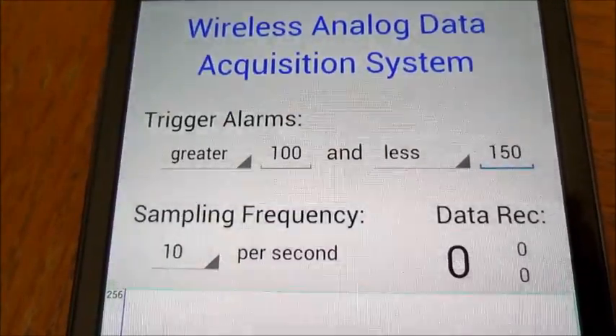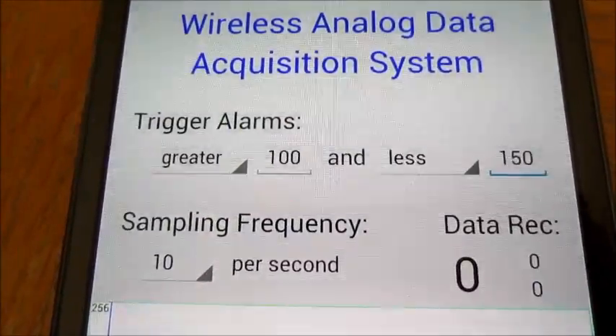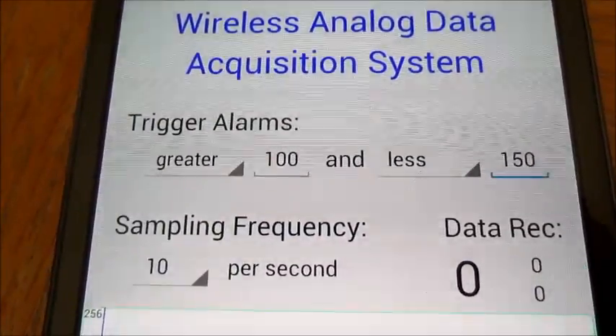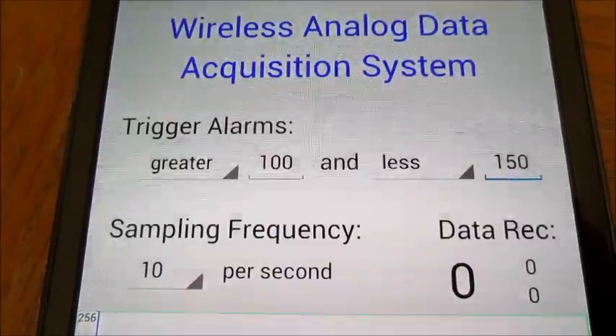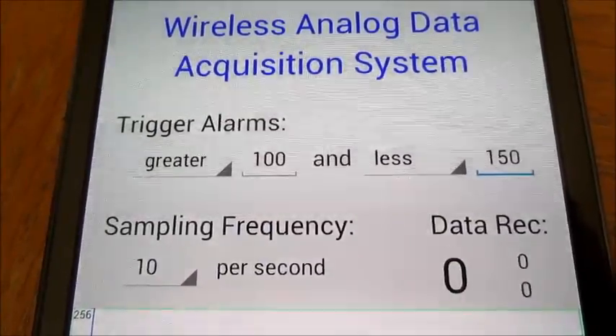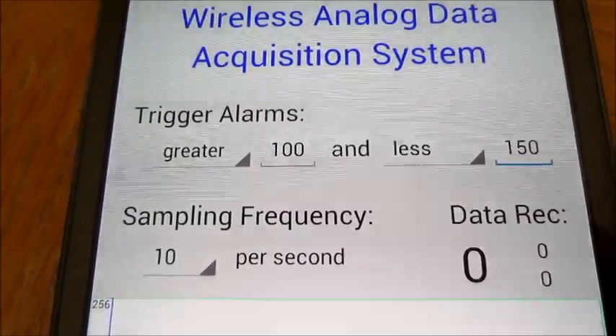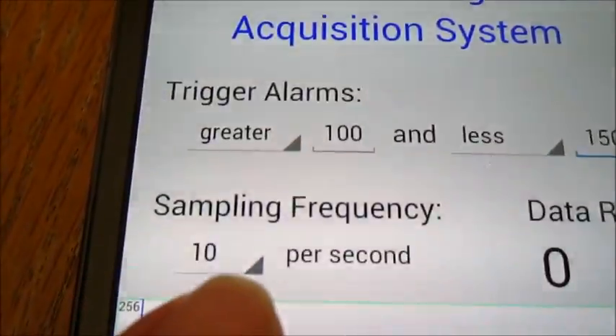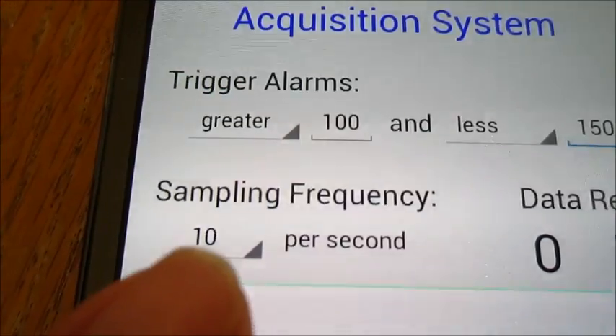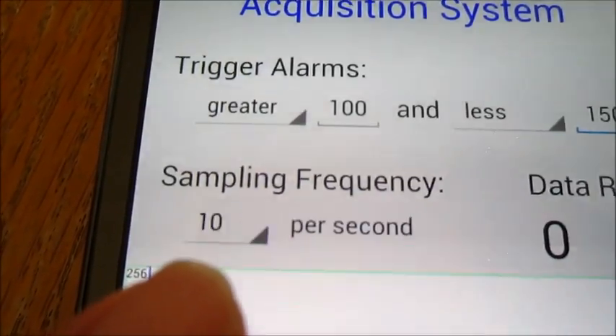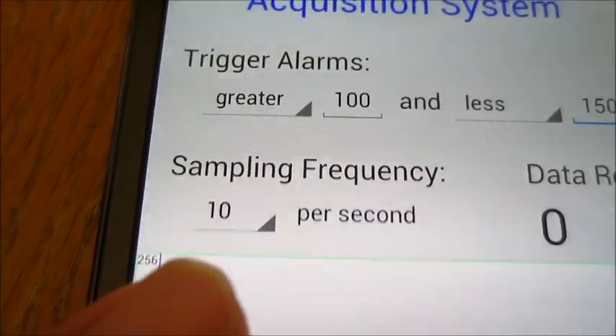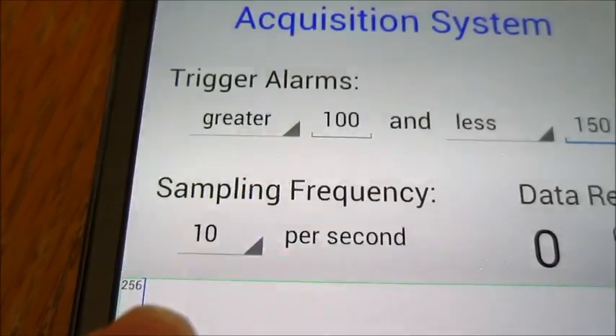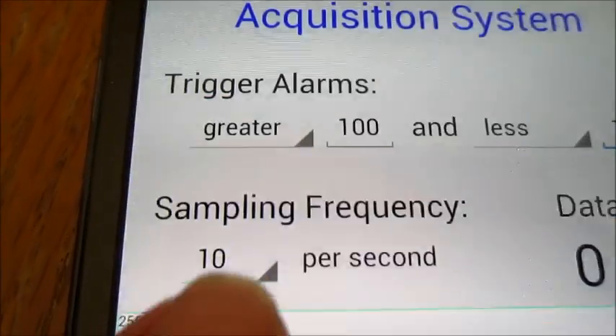Now the alarms are set to be greater than 100 and less than 150. You can also set the sampling frequency. Right now it is set at 10 samples per second. I will set it at 50 samples per second to make it faster.